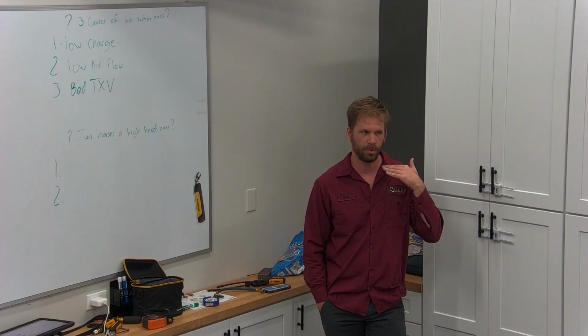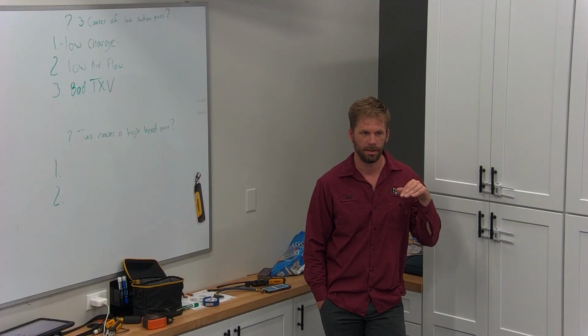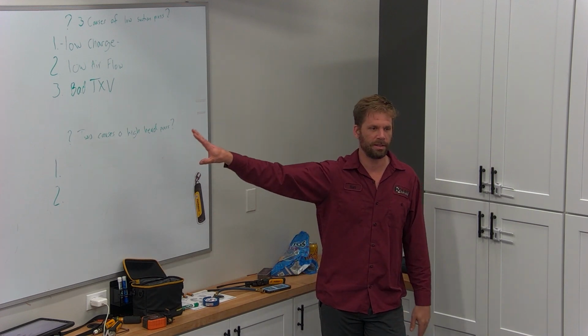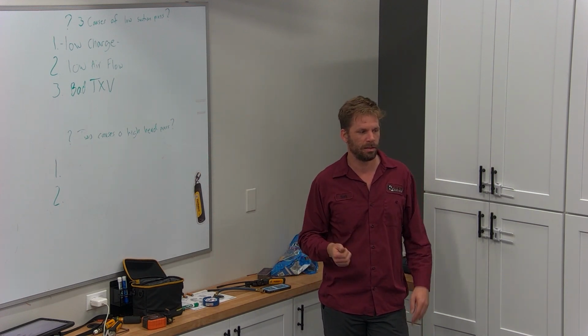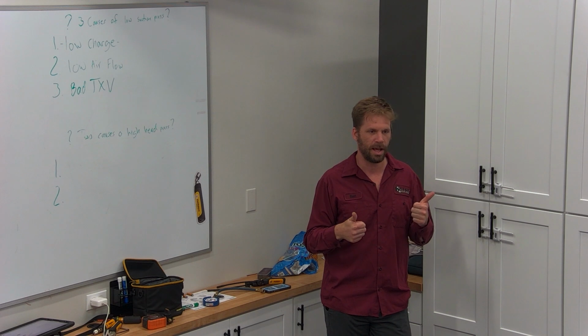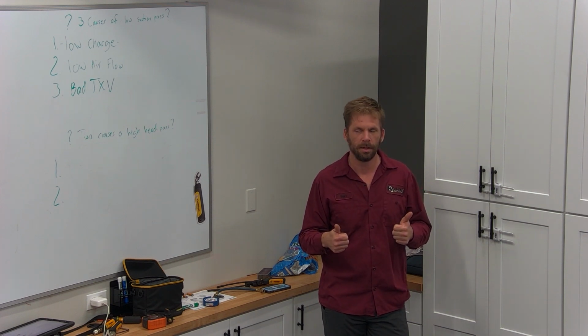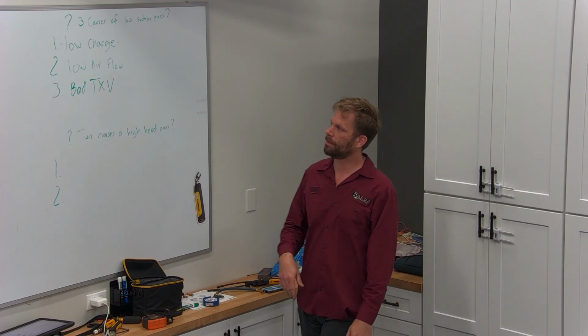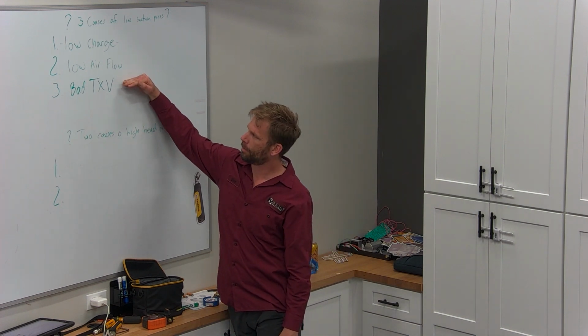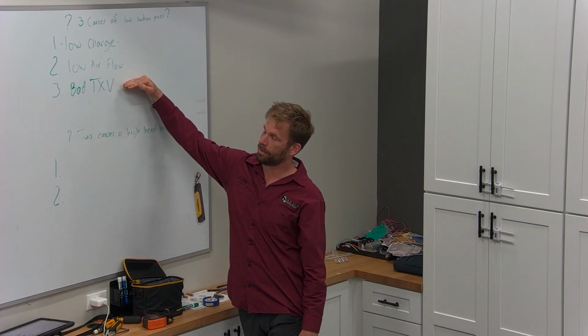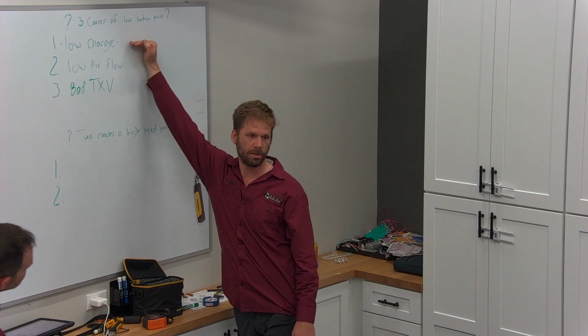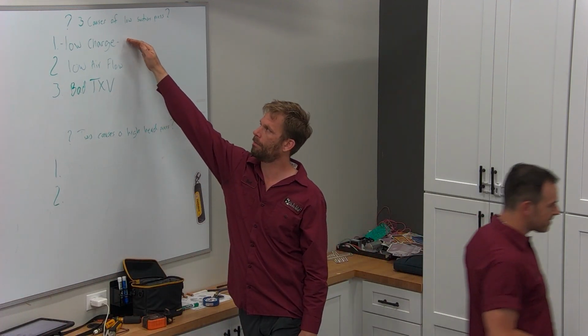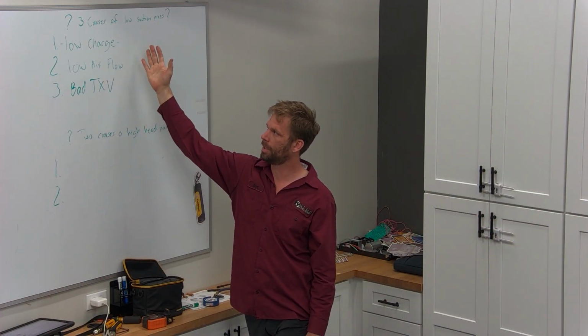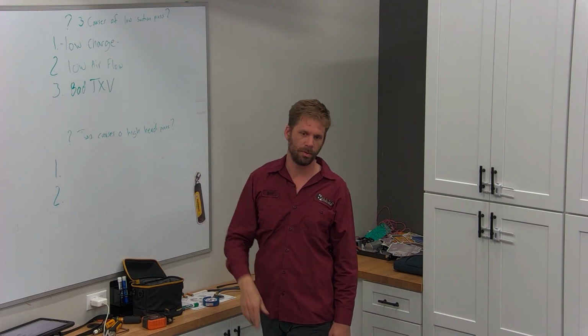That's right. We learned earlier, if our subcool is good, if our subcool is fine, our refrigerant level is fine. So regardless of what we see on that suction, if our subcool is good, we don't need to add charge. That's not what our problem is. So we can now diagnose a bad TXV versus low charge. Both have low pressure and high superheat, but only one has good subcool.